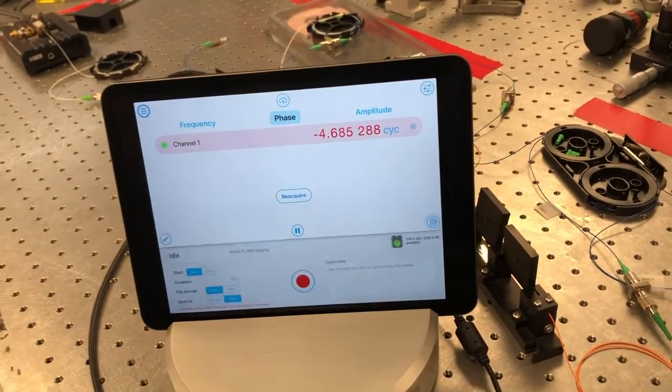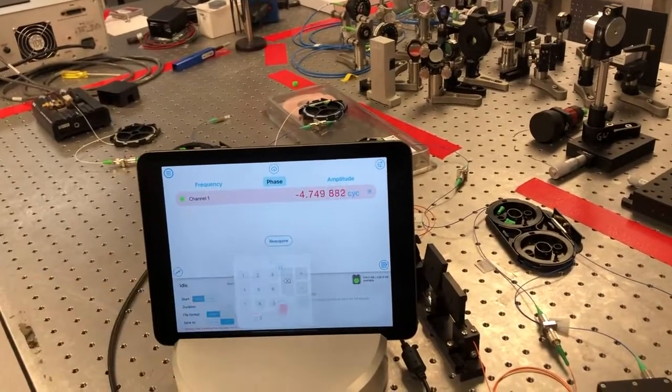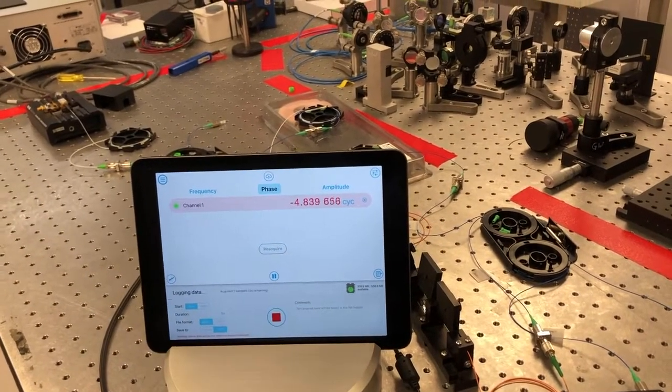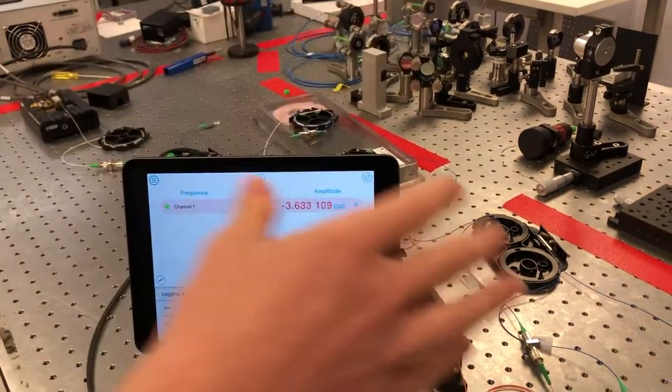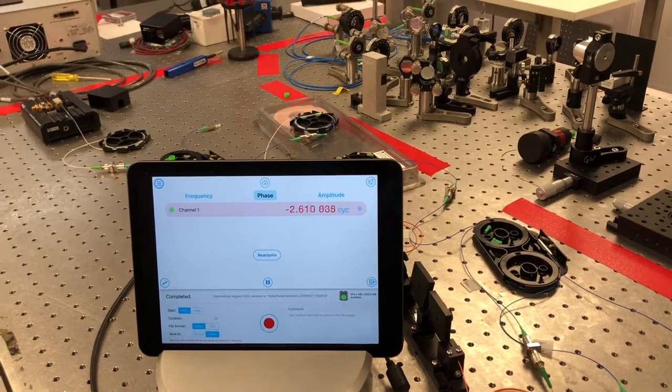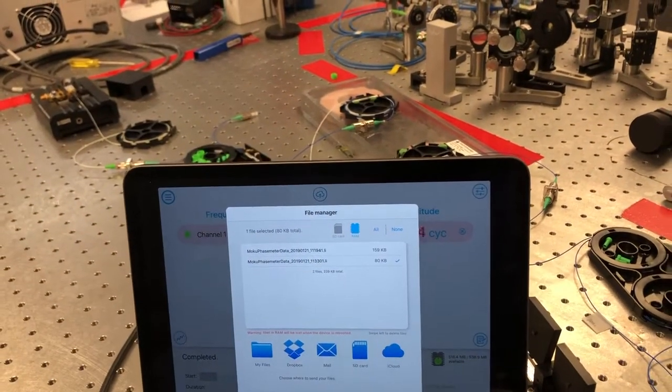What I can do is essentially set up a measurement for, I'm going to say, five seconds. I'm going to save it to RAM on the actual device, and then we'll hit go. And what this is going to do is record the phase difference between these two arms in the interferometer for five seconds. And then once I'm done with it, I can click this icon up here, and then take that data and export it to, in my case, Dropbox.